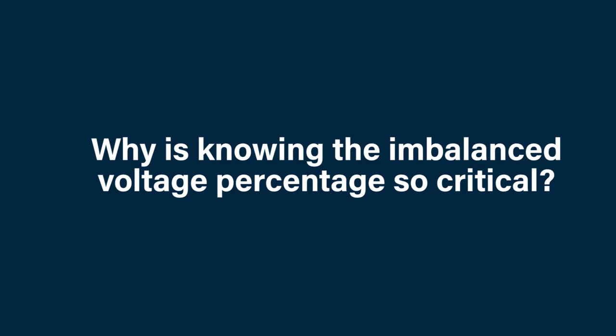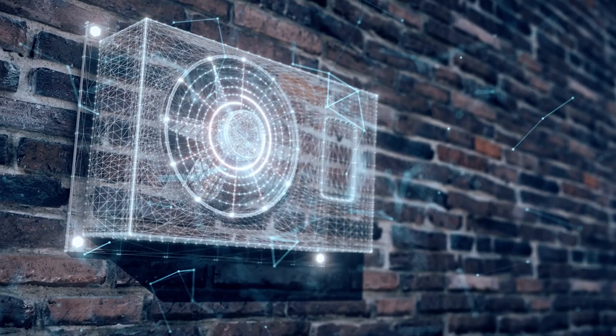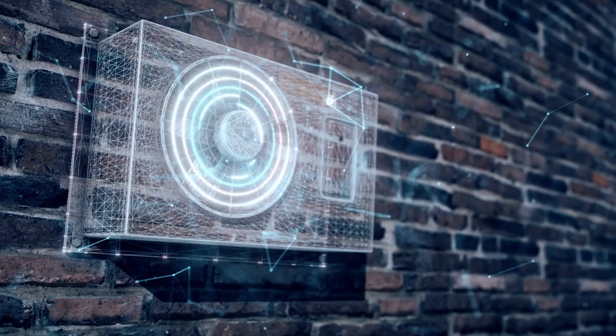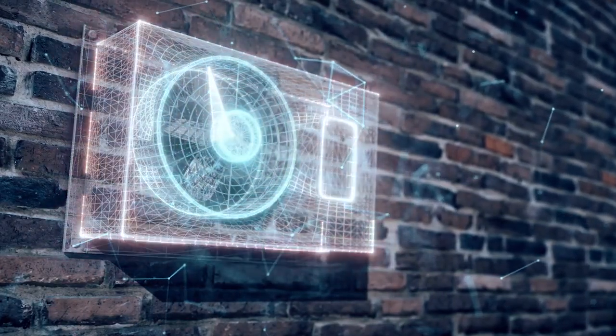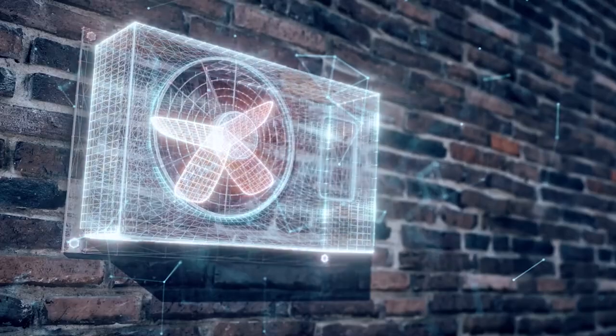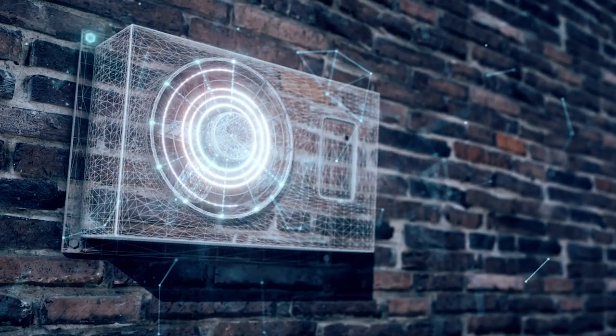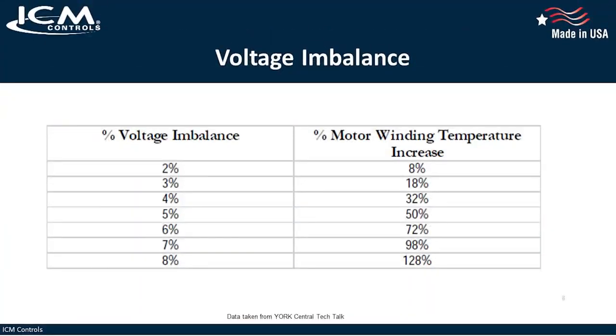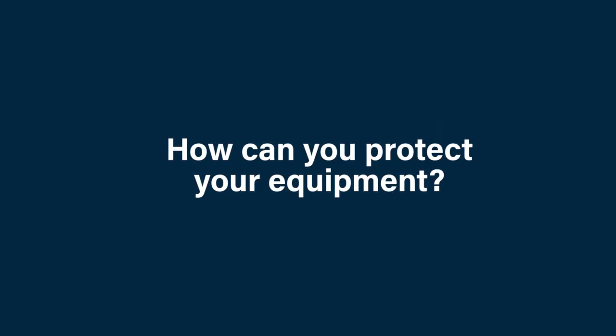Why is knowing the imbalanced voltage percentage so critical? Because when your system is subjected to prolonged periods of a voltage imbalance, the motor windings overheat, and you'll shorten the lifespan of your motor or compressor. This chart illustrates just how much damage voltage imbalance can do to your motor windings. A general rule of thumb is to contact the utility company directly should there be an imbalance approaching 3% or higher. So how can you protect your equipment?